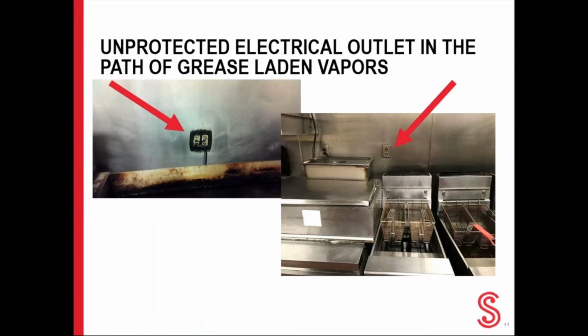Unprotected electrical outlets in the path of grease-laden vapors. As you can see in these photographs, there are exposed electrical outlets located behind the cooking equipment. An open outlet is a fire hazard exposure, as those grease-laden vapors can accumulate inside of the electrical outlet. This may cause an electrical short or spark, which can ignite surrounding materials. The outlet should be removed or refitted with a GFCI, which is also known as a ground fault circuit interrupter type outlet. If there is not one already in place, there should also be a vapor-tight metal snap cover over the outlet to protect it from grease-laden vapors.